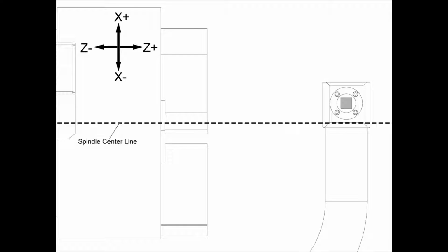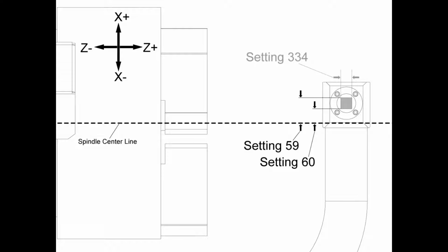There are 4 settings used to establish the position of the ATP stylus. Setting 59 is the distance between the X-positive face of the stylus and the spindle centerline. Setting 60 is the distance between the X-negative face of the stylus and the spindle centerline. Setting 334 is the Z-axis probe width. Setting 333 is the Z-axis probe offset.